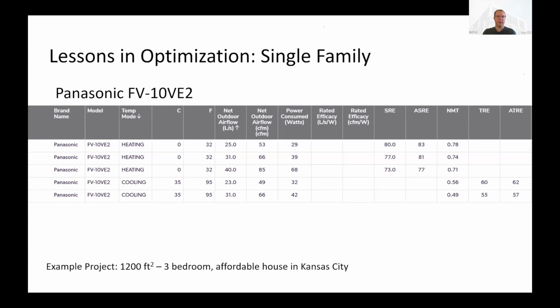All right, so let's look at the small single family first. So this is a 1,200 square foot, 3-bedroom, super affordable house for an affordable program in Kansas City. And they ended up installing a Panasonic right here. So it's the 100 CFM version of the Panasonic, like IntelliBalance, I think. So when we look at that, we can see, again, same things we've been looking at. When it's at 53 CFM, we have apparent sensible recovery efficiency up at 83. As we move to 85 CFM, that drops down to 77. So that kind of 6% difference there.